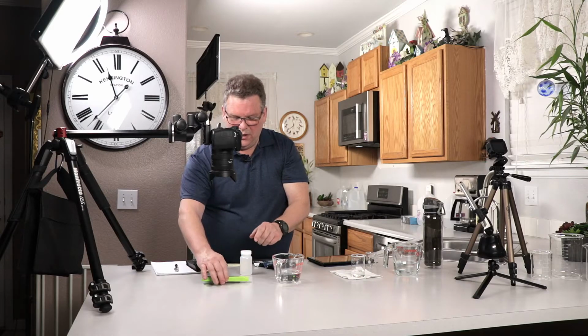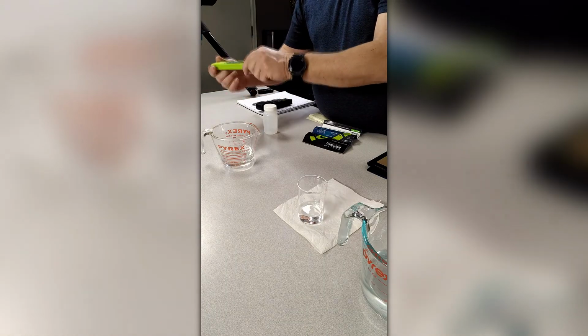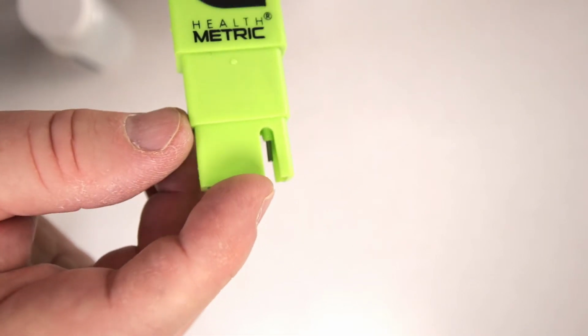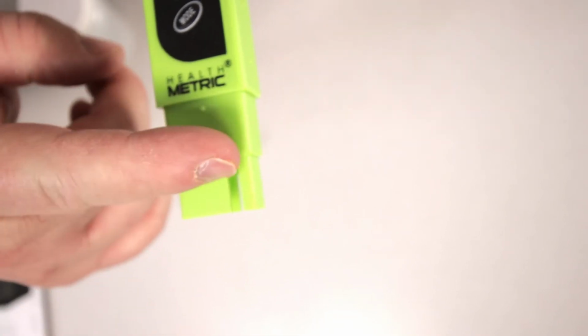And what I'm going to do is I want to show you on these meters. It's very important that you don't go too far up from the bulb. So you'll see that there's a bulb inside of this cutout, and then you start getting into this area where the sheath actually gets to it. If you dip this meter above that area that the sheath cover attaches to, you are now getting into the electronics and the solder points, and you might as well just throw this away.